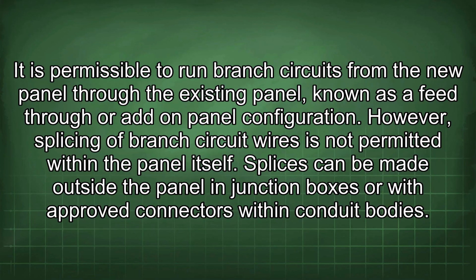It is permissible to run branch circuits from the new panel through the existing panel, known as a feed-through or add-on panel configuration. However, splicing of branch circuit wires is not permitted within the panel itself. Splices can be made outside the panel in junction boxes or with approved connectors within conduit bodies.